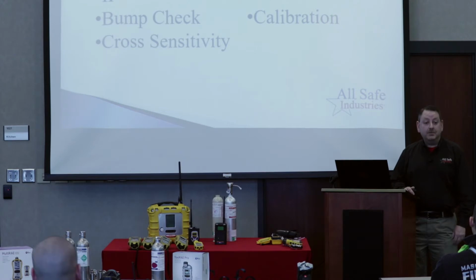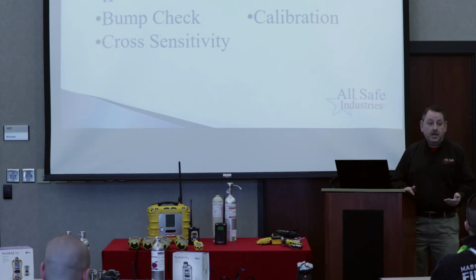So a good example of that is your carbon monoxide sensor will have a cross-sensitivity reaction to the calibration gas we use on the PID, which is isobutylene. So nothing to be alarmed about. It's just you want to calibrate your CO sensor first so that then when you're calibrating the PID with the isobutylene gas, any cross-sensitivity won't matter because you've already calibrated the CO sensor. But it's important to know when cross-sensitivities may exist.